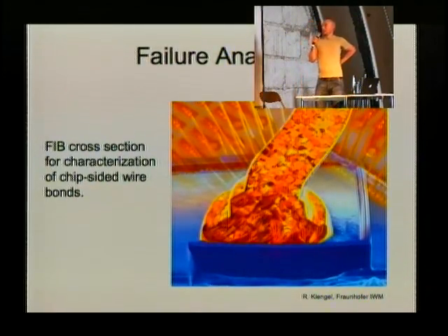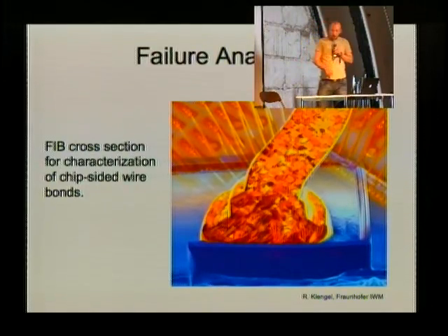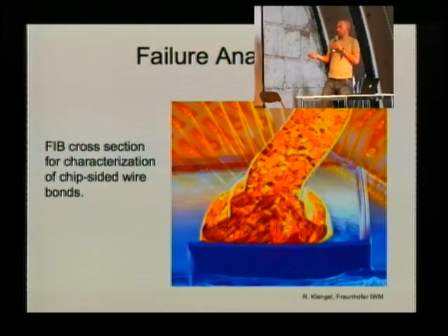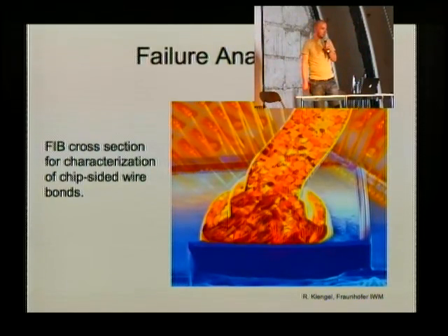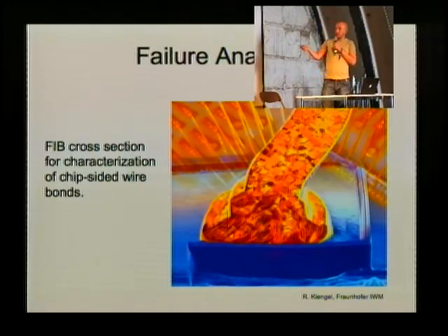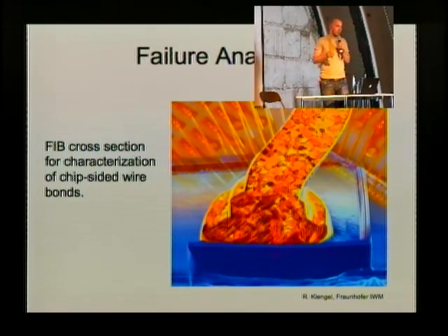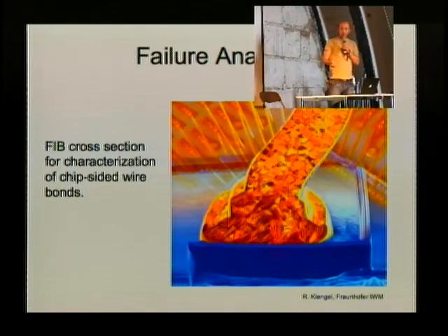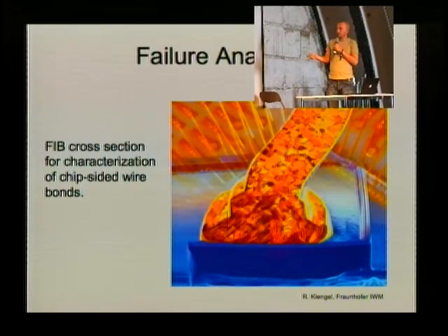So, why is it so nice for failure analysis? What we see here is the chip-side bond of a gold wire, and there are many factors governing how this wire bonds. This is a common cause of device failure, that one of these wires breaks or gets detached from the substrate. So the FIB allows you to cut the soft wire and cut through the very hard silicon without changing the surface. You can nicely see you get a very clean cut, exactly where you want it to be. And you can later have a very close look at this contact surface between the bond and the chip.